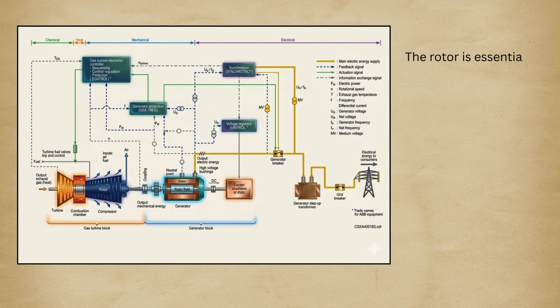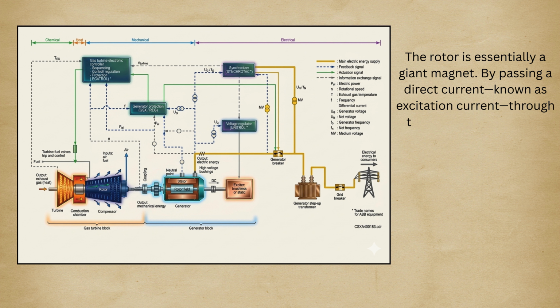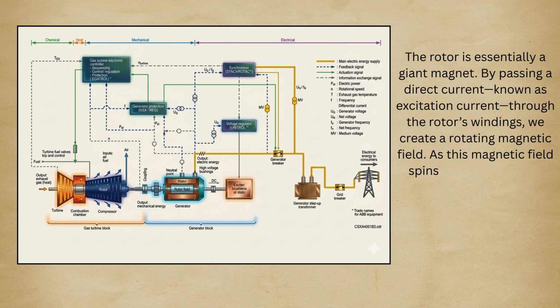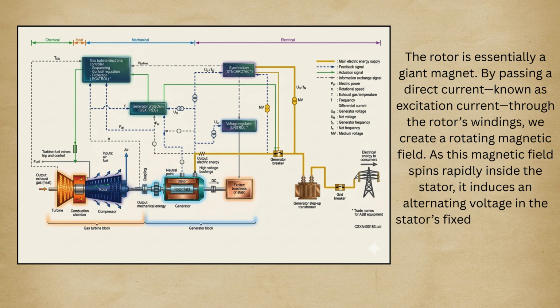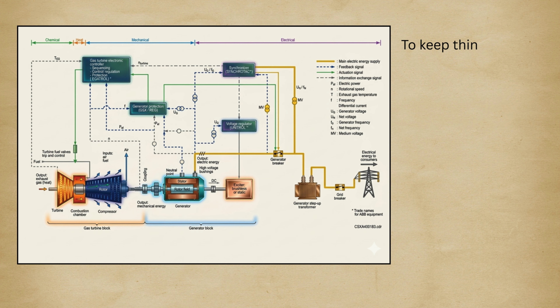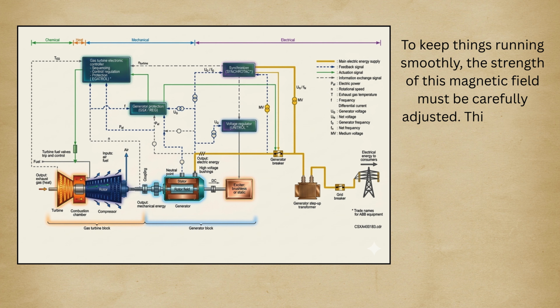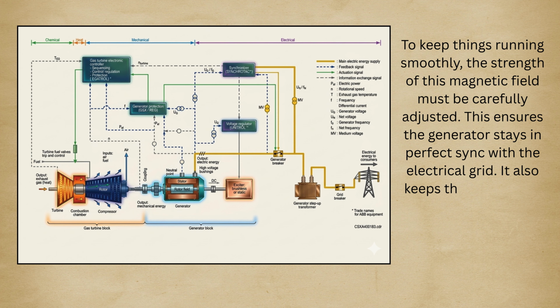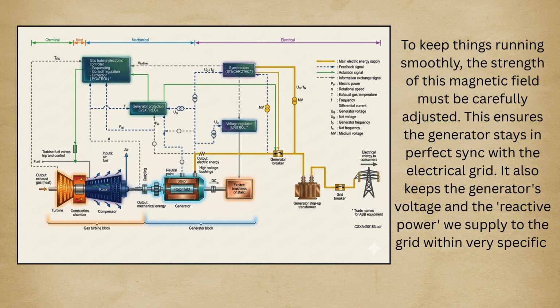The rotor is essentially a giant magnet. By passing a direct current, known as excitation current, through the rotor's windings, we create a rotating magnetic field. As this magnetic field spins rapidly inside the stator, it induces an alternating voltage in the stator's fixed windings. This is the exact moment where motion becomes electricity. To keep things running smoothly, the strength of this magnetic field must be carefully adjusted. This ensures the generator stays in perfect sync with the electrical grid. It also keeps the generator's voltage and the reactive power we supply to the grid within very specific, safe limits.